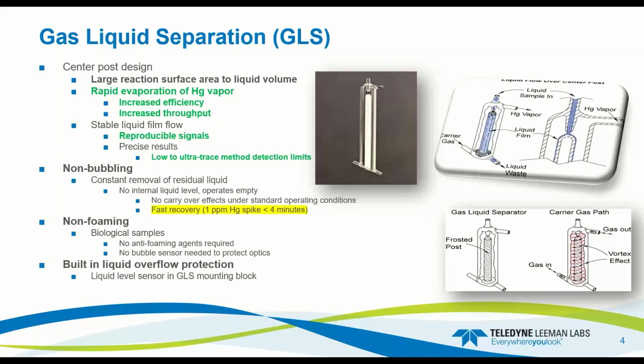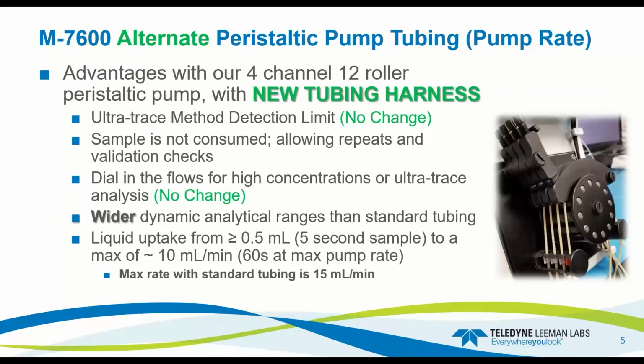It would stop the peristaltic pump and tell you that you have an issue with the waste line. Now we segue into the peristaltic pump. So this is a 4-channel, 12-roller pump. Ultratrace detection limit, so that hasn't changed from the original pump tubing harness. Samples not consumed, that's still the same.